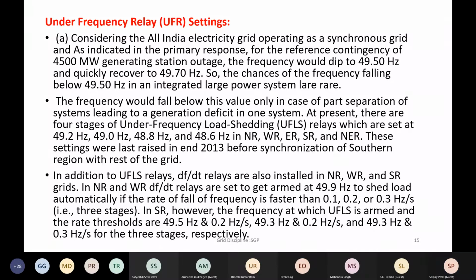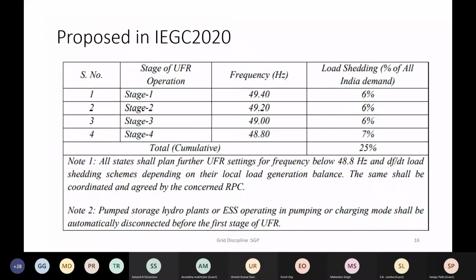But if the region becomes split, for example, certain regions get disconnected, like in the 2012 grid collapse, when the western region and northern region got separated and all the power flow went via the eastern region, these types of phenomena can be handled through proper load control measures as well as the special protection scheme. They have to be very well coordinated with the frequency control measures at the generating power stations and the controllability of the primary control as well as the secondary and tertiary control of the frequency. So all three stages of frequency control are important to keep the frequency within the desired narrow band. These are some of the measures you can see.